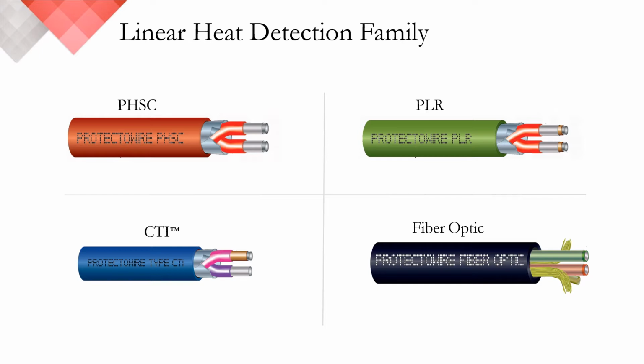And lastly, we have fiber optic, which is widely viewed as the next generation in linear heat detection. Standard digital linear heat detection is considered a passive device, meaning it sits in a ready state, waiting for the fixed temperature to be achieved before it activates. Fiber technology, on the other hand, is an active system that reports real-time temperature profiles anywhere along its length, up to 10 kilometers. That's a little over 32,000 linear feet. And this is all done off a single fiber. And this can further be segmented or zoned into 256 unique partitions anywhere along its length, which is all done through software.